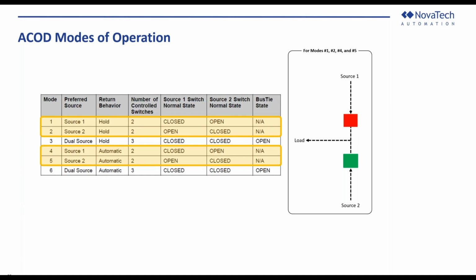All right, next I'd like to go over the modes that ACOD can be configured for. The 6 possible modes are shown here in this table. The highlighted ones, 1, 2, 4, and 5, do not utilize a bus tie. So therefore, it's one source operating at a time. To the right is a one-line diagram demonstrating what this implementation would look like.